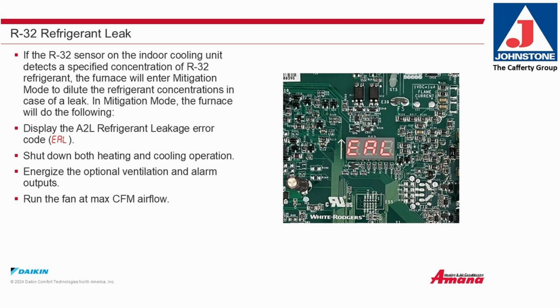R32 refrigerant leak. If the R32 sensor in the indoor cooling unit detects a specified concentration of R32 refrigerant, the furnace will enter mitigation mode and dilute the refrigerant concentration in case of a leak. In mitigation mode, the furnace will do the following: display A2L refrigerant leakage error code, shut down both heating and cooling operation, energize the optional ventilation and alarm outputs, run the fan at maximum CFM airflow.